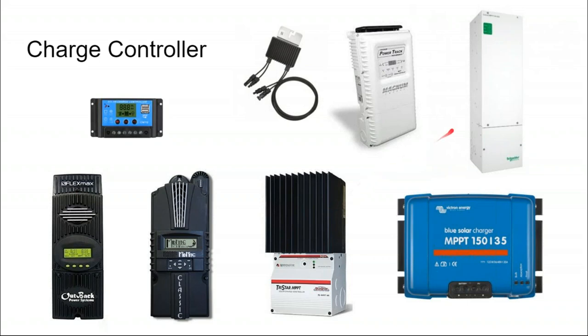It starts to become real interesting because charge controllers are different than solar inverters. Solar inverters are designed to take every kilowatt hour that comes out of the array and do something with it. Whereas a solar charge controller is more concerned about the battery itself than taking every volt out of the array it possibly can. Charge controllers are more about monitoring the battery state of charge and charging it in a way that's best for the battery, assuming it can be fed with a power supply, rather than starting with the power supply and trying to force every kilowatt hour out of it.